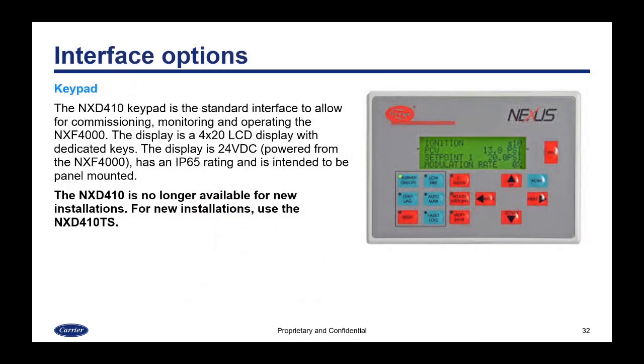We have some different interface options for the NXF4000. The first is the keypad NXD410, and I'll skip right to the note that this is no longer available for new installations, but this is going to be very common for existing installations. This is the standard interface to allow for commissioning, monitoring, and operating the NXF4000. It's a 4x20 LCD display with dedicated keys, and it is 24 volt DC powered, and it's powered from the NXF4000.